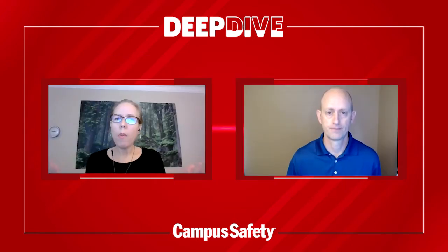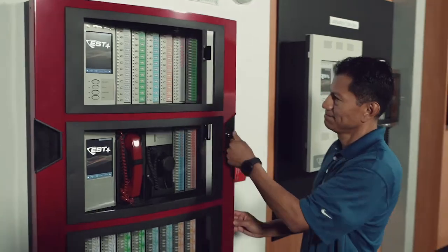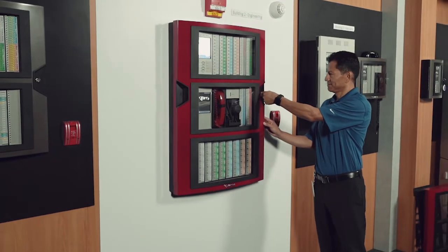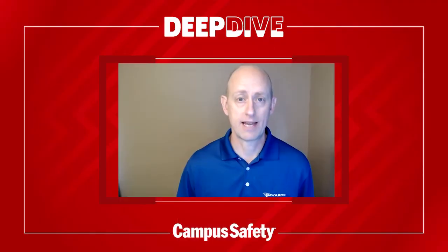So a fire panel isn't just a fire panel anymore? Correct. Because campuses must connect multiple buildings, up-to-date fire panels utilize modular architectures that incorporate innovations in network configuration, audio, circuit survivability, and when connecting to external networks, adequate levels of cyber security. And of course, all of this has to be done while complying with local codes and industry standards.